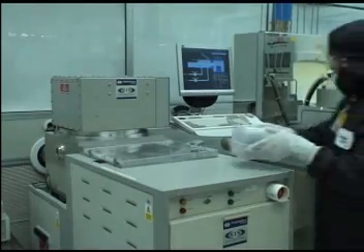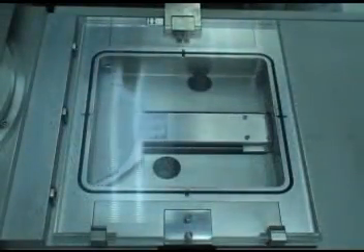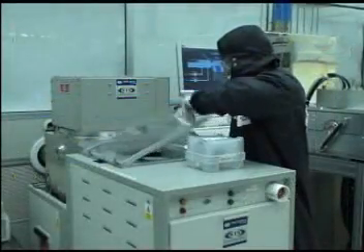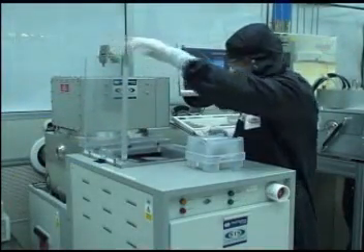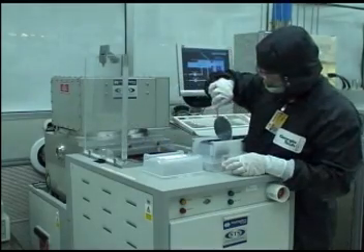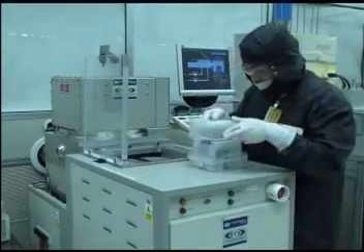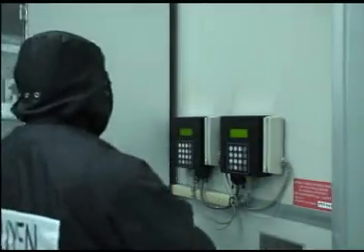Once the process is complete, you may remove your sample. Press the F3 button to access the load-unload feature, then press U to unload the sample. You will know that the load lock is vented when the chamber pressure reaches approximately 760 torr. At this point, the load lock may be opened and your sample can be removed. When you are finished, close the load lock and run a cleaning process by pressing F2 and selecting the clean dot set recipe. When it is complete, log out of the system at the access controller.